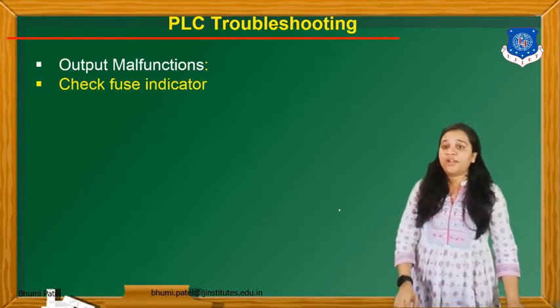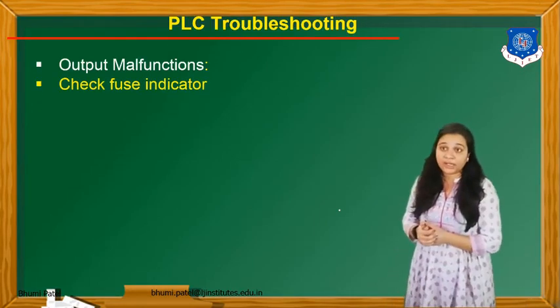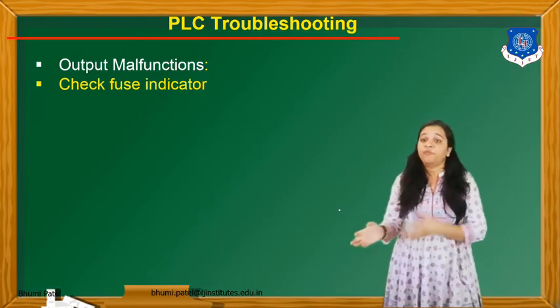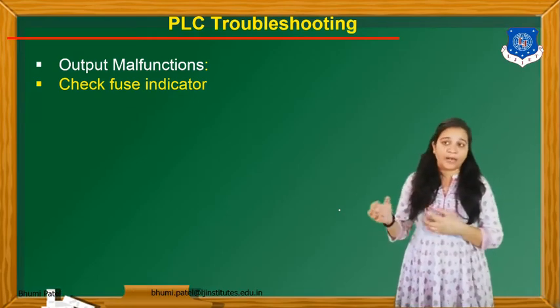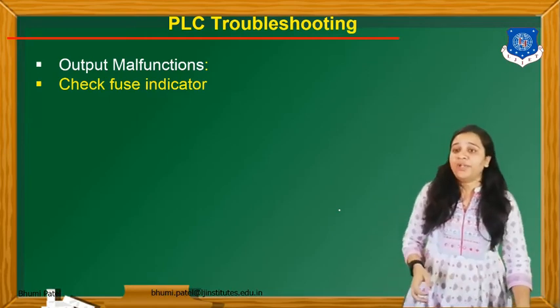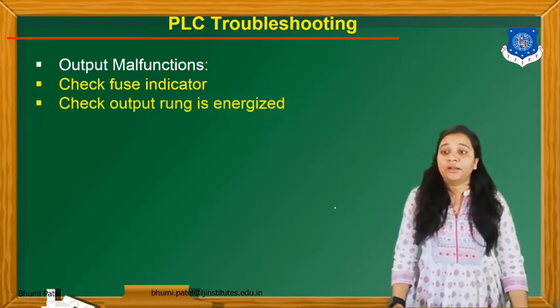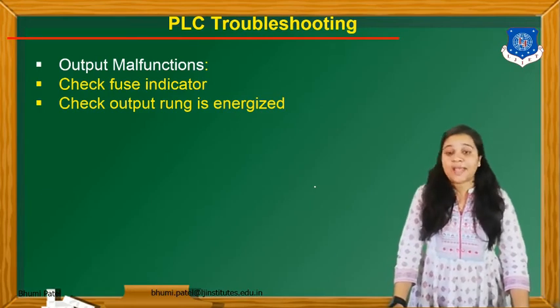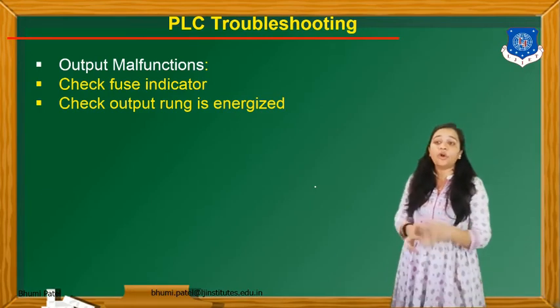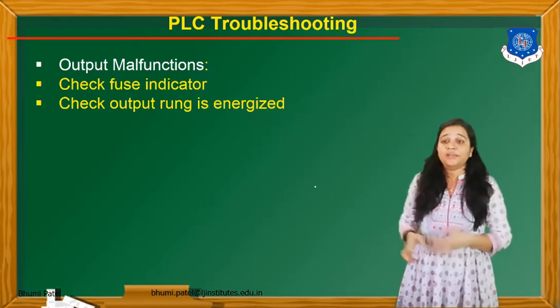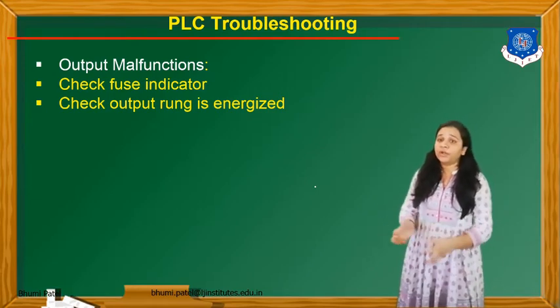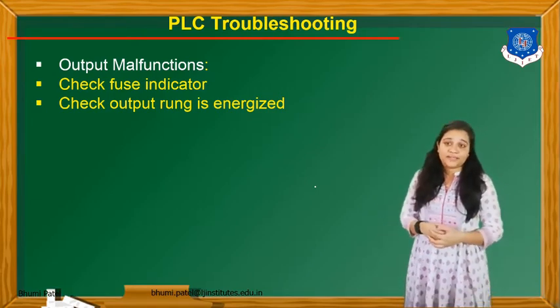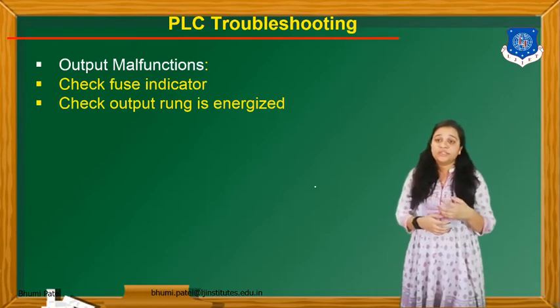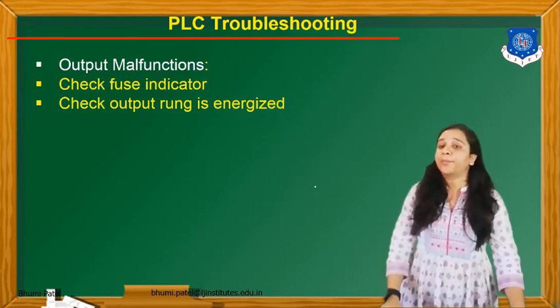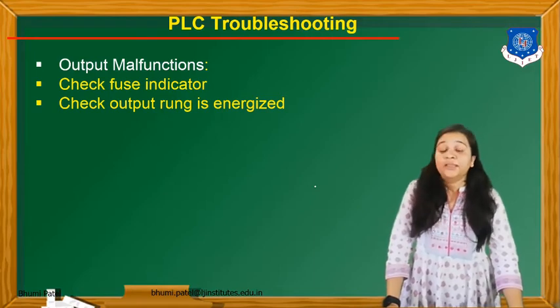In the output malfunctions, we can check the fuse indicator, if we connect an alarm, fuse, indicator or recorder as the output device. Then we check whether the output rung is energized, because if we load the program to the hardware but in the software the output rung is not on or energized, we cannot check the output properly. So first of all, we check whether the output rung is properly energized or not.